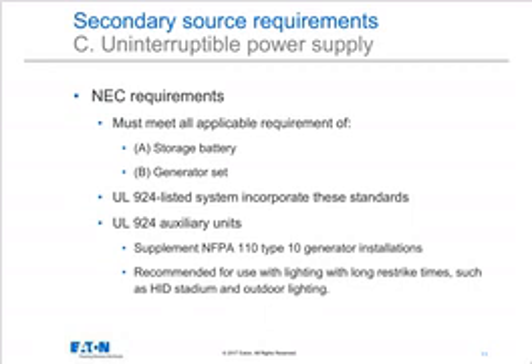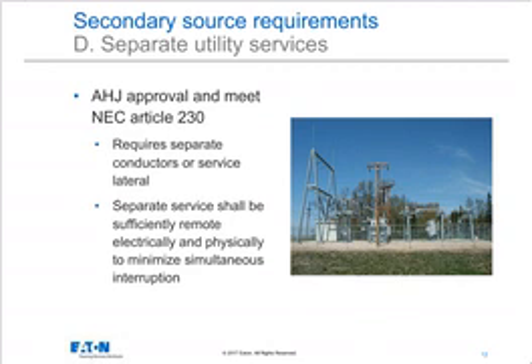Separate utility services. This is what we were talking about briefly a moment ago, where I have multiple utility sources to a building. This is not common unless it is a mission critical application like a data center. Hospitals are another application that would be at least a possibility for having separate utility services. And the idea is if one utility service fails during a thunderstorm, for example, the other utility service can power that building. So it means they need to be truly separate. I need separate conductors at 2 different places in the building, and I'd like for them to be sufficiently remote, both electrically and physically, to minimize the chance of them both failing or being interrupted at the same time.